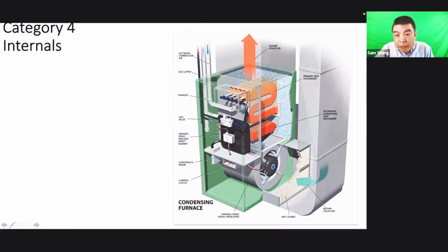And sometimes, like in this picture, we can see this motor has no openings on the end. That's what I talked about before. You should check or take a picture of the end of the motor here. Because it's an AC motor, there's a small circulation hole there that makes air circulate and cool down the coil inside. Normally the end of the motor will be very dirty. If you find that, you should make notes and let the customer know.